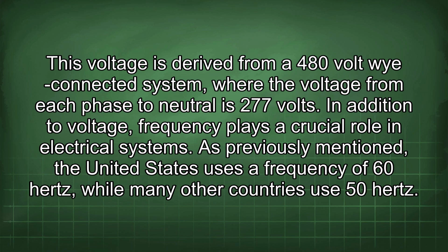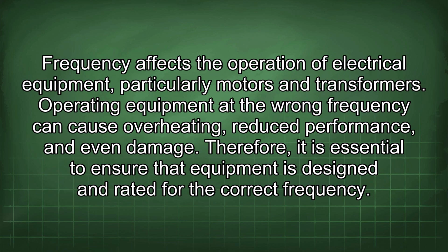In addition to voltage, frequency plays a crucial role in electrical systems. As previously mentioned, the United States uses a frequency of 60 Hz, while many other countries use 50 Hz. Frequency affects the operation of electrical equipment, particularly motors and transformers. Operating equipment at the wrong frequency can cause overheating, reduce performance, and even damage. Therefore, it is essential to ensure that equipment is designed and rated for the correct frequency.